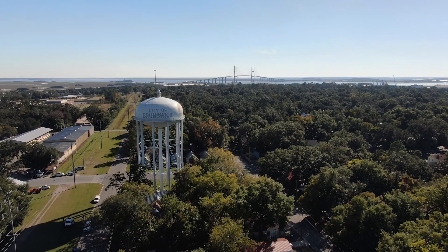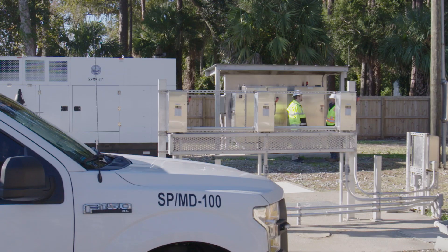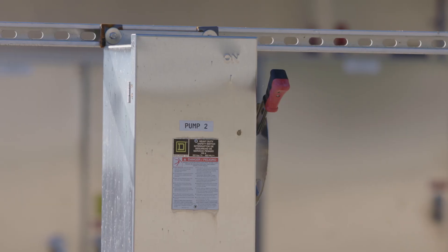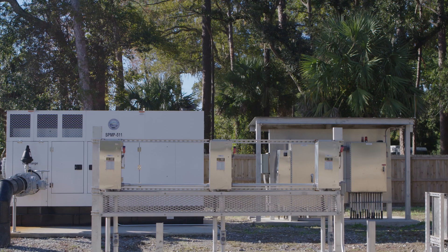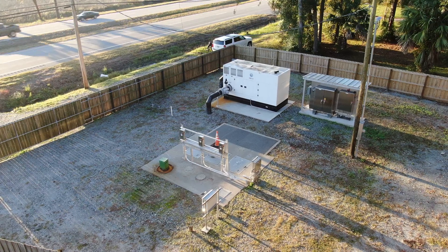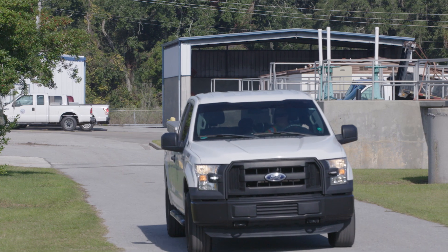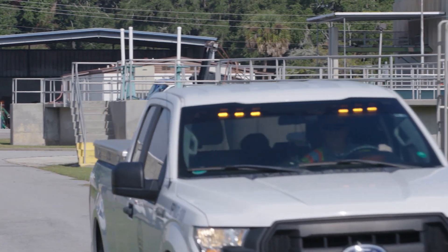In this flat environment here on the coast we get a lot of severe thunderstorms. We were seeing a tremendous amount of electronics being lost due to lightning strikes or power surges or brownouts. This was leading to devices that were unreliable because their radios would go. That repeated failure led to continuous repairs. When you have 160 devices, that's very, very frequent.